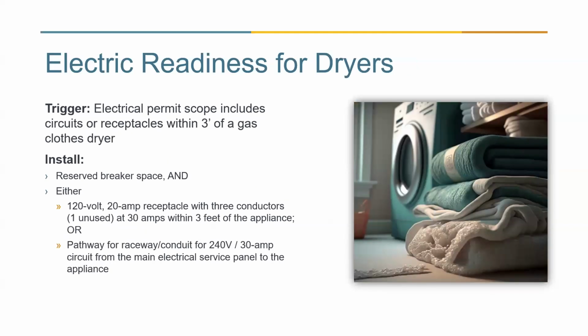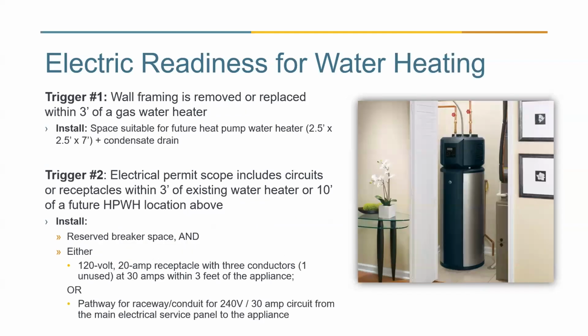For dryers, the installation is basically the same as for the cooktops or stoves. And the trigger for this would be any electrical permit scope that includes circuits or receptacles within 3 feet of an existing or proposed gas clothes dryer. For a water heater, again, a similar trigger: if circuits or receptacles are permitted within 3 feet of an existing water heater, or additionally, if wall framing is removed or replaced within 3 feet of a gas water heater, that would also trigger the requirement.